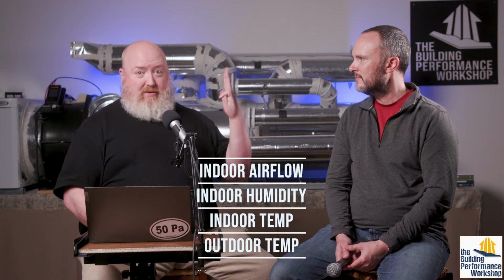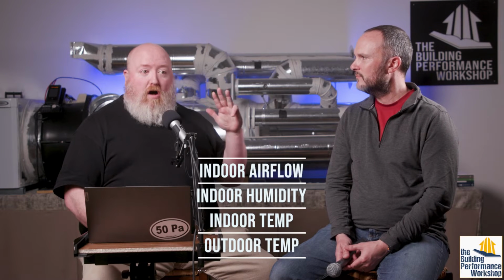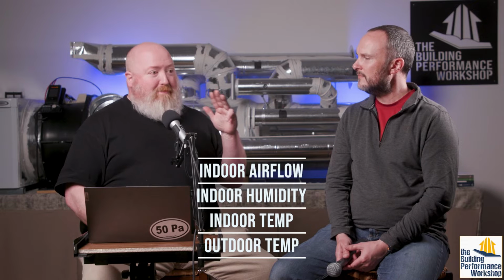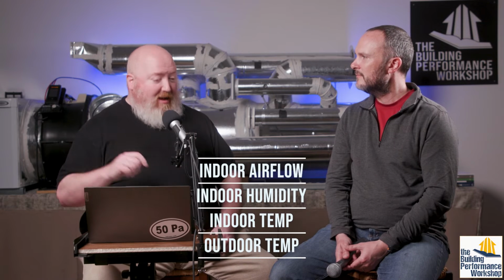It's called a wet bulb temperature, and lots of psychrometric stuff—temperature, pressure, and moisture—is interactive. It's hard to know one without the others. So I want to know the indoor dry bulb, the indoor wet bulb, and the outdoor dry bulb. If I don't know those things, I don't know how the system performs. Your HVAC guys know that—they've looked at a pressure chart. When they charge these things, they have to adjust for outdoor temperature and indoor humidity. And by the way, I left one off: the CFM, the airflow.